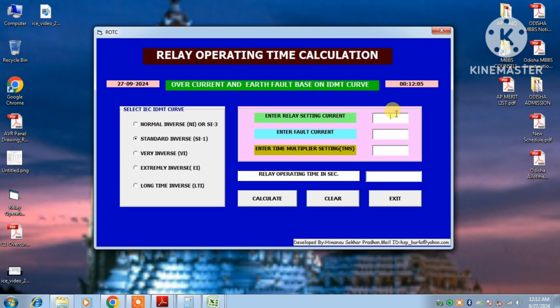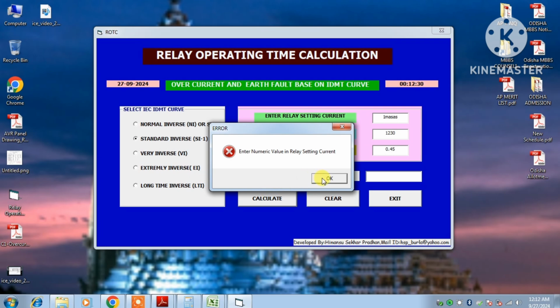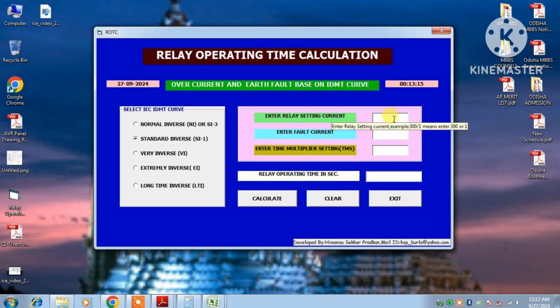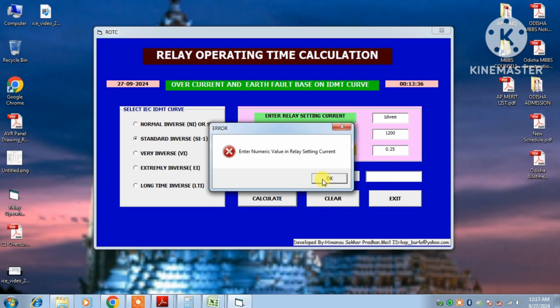One more important feature in this application is that you need to enter the setting current in numeric value only. If somebody enters an alphanumeric value, just entering roughly, then when you calculate, a message will automatically come asking you to enter a numeric value. Suppose I enter 1 2 3 4 like this, it will not accept. Suppose the fault current is 1200 and the TMS is 0.25. You can get the TMS value in the relay setting file. If it is not given, you can take it as 1. If you calculate it, it will not accept.